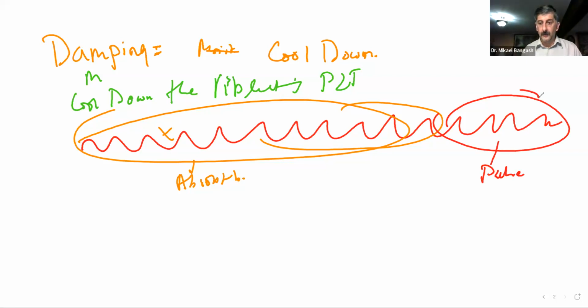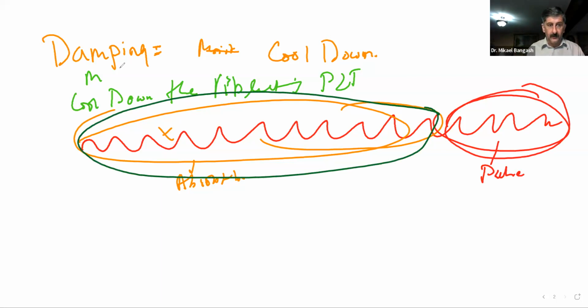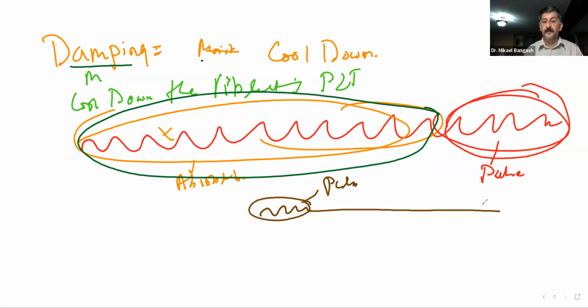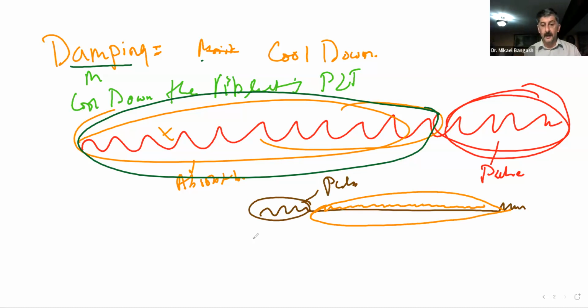Is that clear? It produces a pulse like this, because all these sound waves here were absorbed or damped by the backing material. That's how it works. A transducer with backing material will just produce a short burst of cycles, which we call a pulse. That will be followed by an off period, off time, followed by another pulse. Whereas had it not been for the damping material, all this area here would also have had sound waves, and it would have been a continuous wave.